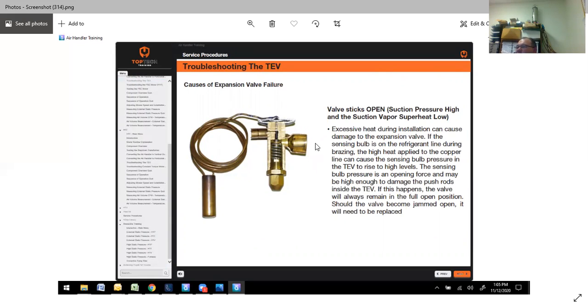Now, with TEVs, expansion valves, they have enough problems on their own, but proper installation practices, brazing, flowing nitrogen as you're brazing, not overheating things, will save you a ton of problems down the road. Excessive heat during installation can cause damage to the valves. If the sensing bulb is on the refrigerant line during brazing, it will affect the levels in the TEV bulb. The sensing bulb pressure is an opening force and may be enough to damage the push rods in the TEV. So, seeing guys do it, you know, it's not a good practice. If this happens, the valve will remain in the always full open position.